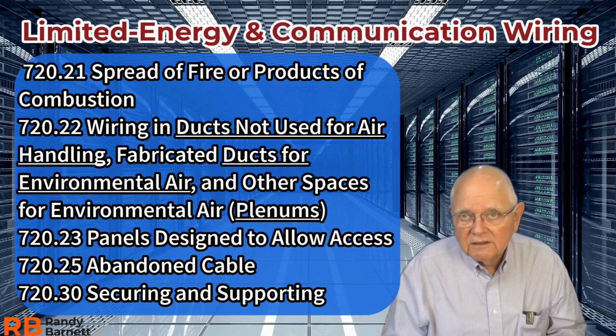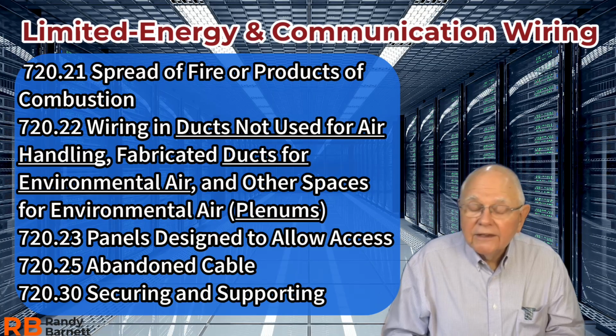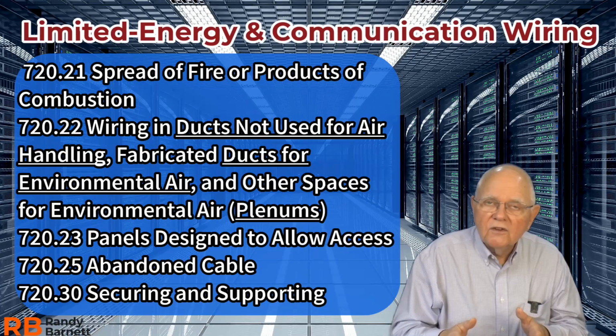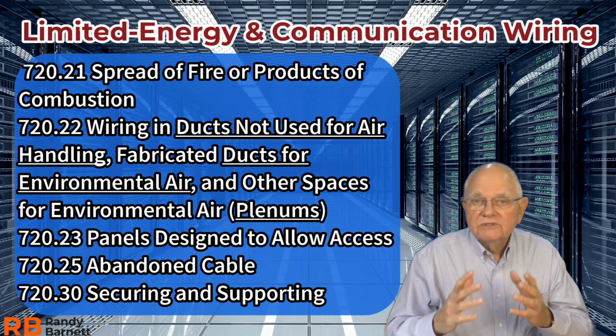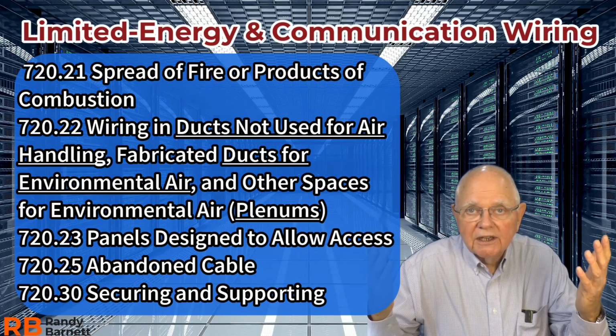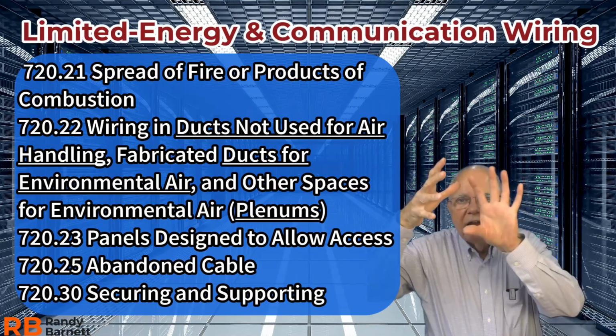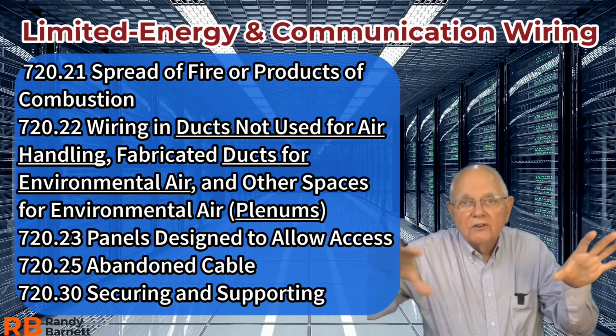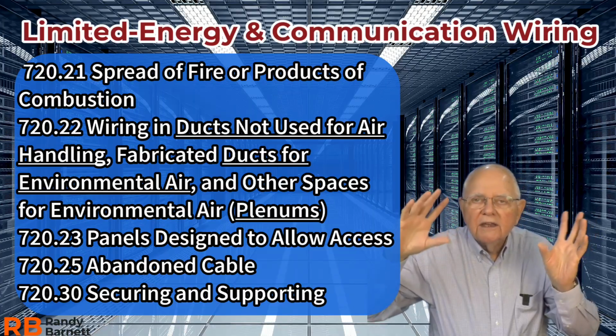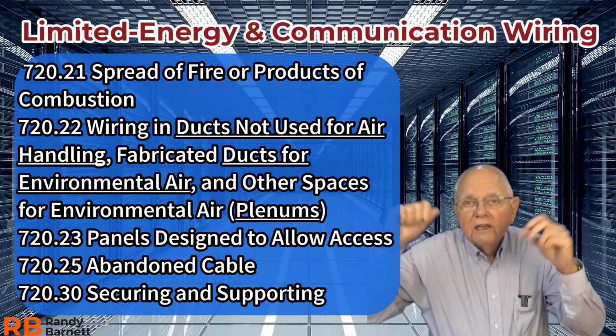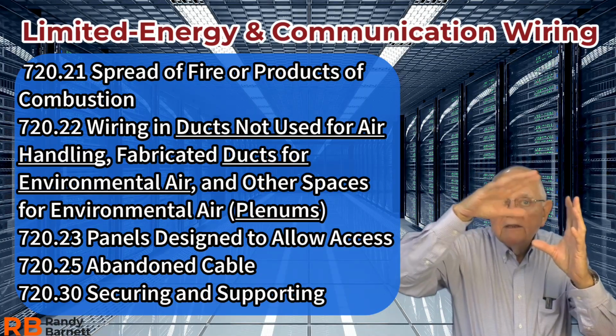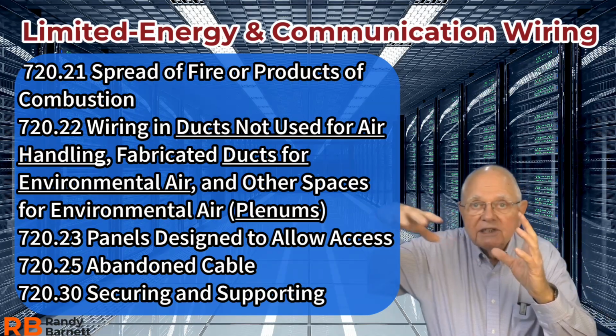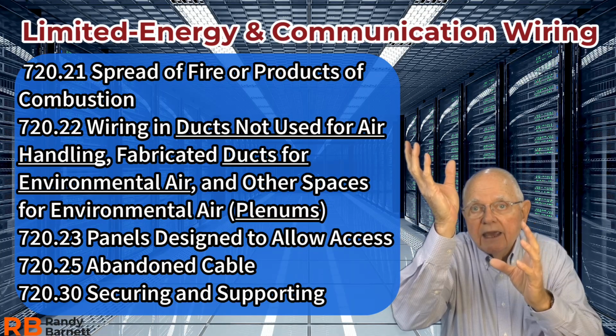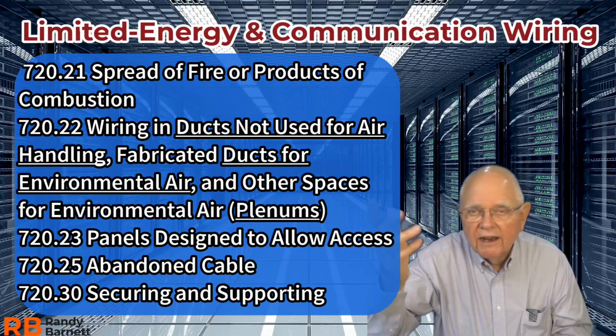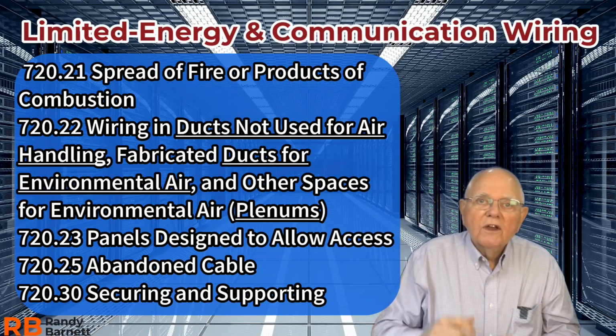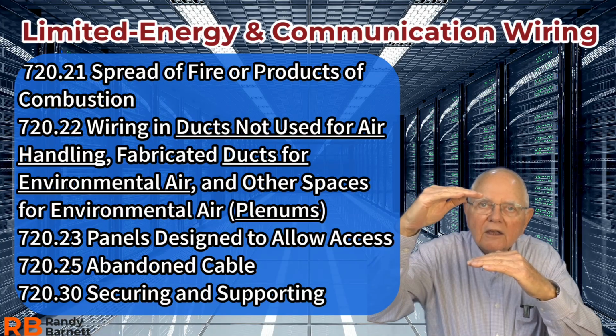And then finally, the third area that they're talking about, this other spaces for environmental air. And the code even mentions this in the informational notes, not only within this article, but elsewhere. And it talks about that these spaces are typically what? Above a suspended ceiling. So what do I have? I've got my rooftop unit up here, and I've got my fabricated ductwork that brings my ventilation air in and distributes it throughout the building. And then within that suspended ceiling, I have certain tiles that have vent work in them so that air can return back up through the vent work and be pulled across the top of the ceiling tile and then back into that rooftop unit up top and get heated or cooled, whatever, mixed with some outside air. And then that whole distribution system just continues. So those areas above that suspended ceiling where I have that return air, we call those plenums.